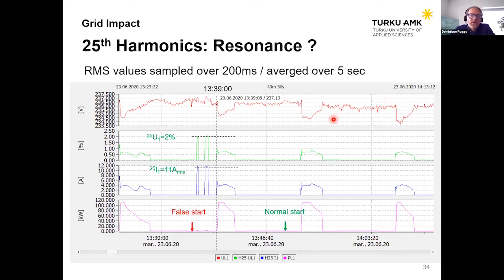Now, looking more closely at the time, voltage, and power, we can see these cycles, the normal charging cycles as before. The impact on the supply voltage shows this 2 volt voltage dip, very normal. But what we see are kind of false starts, where nothing happens or just a brief variation occurs. During this false start, we see exactly our oscillations at 1,200 to 1,300 Hertz, and the current value is pretty high. So this is not normal behavior.